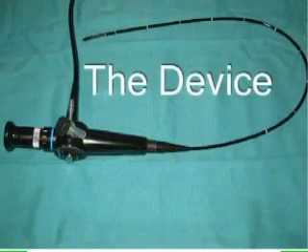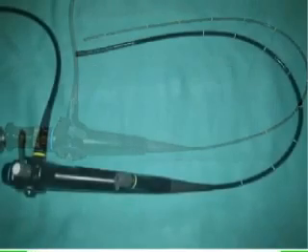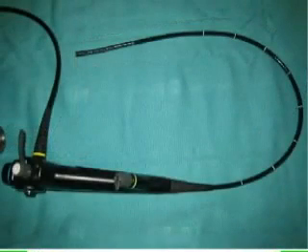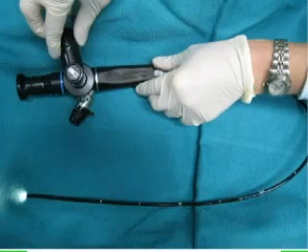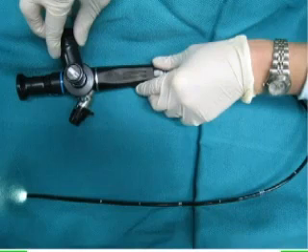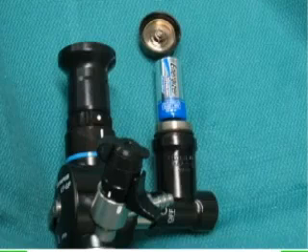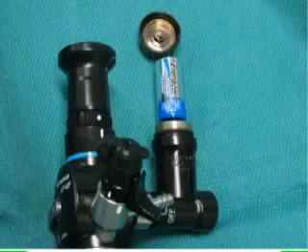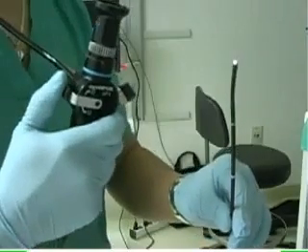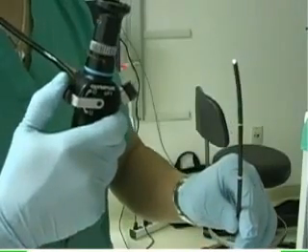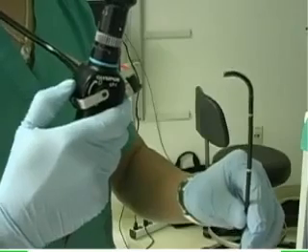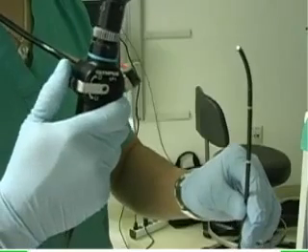Modern flexible bronchoscopes include fiber optic bronchoscopes, video bronchoscopes, and hybrid designs. Flexible fiber optic bronchoscopes are also available with battery operated light sources, which greatly improve portability. The handle of the bronchoscope is fitted with a lever which controls flexion and extension of the tip of the bronchoscope in a single plane.